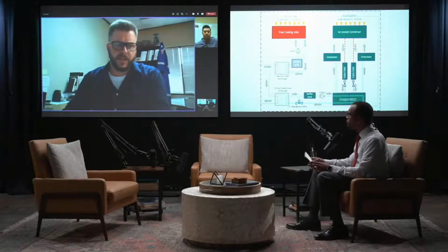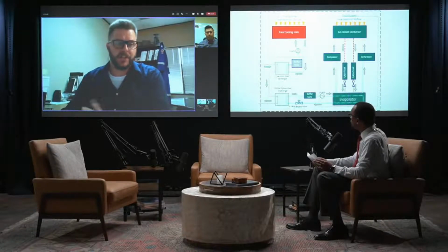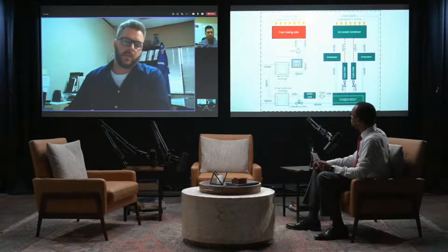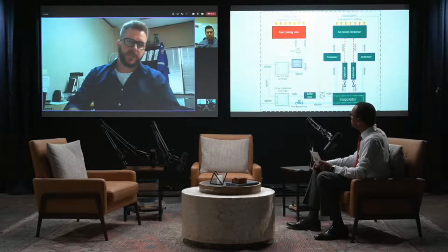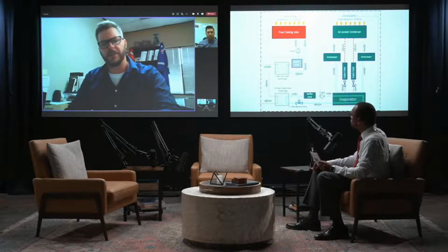And then the second stage is the HVAC system. So again, the closed loop water system. The water flows through a chiller. It's basically a refrigeration system. It's a 150-ton rated unit, so it's got a massive amount of power, or a massive amount of energy that it can take out of that water, which is just heat. So it maintains that water temperature, and then that water enters the heat exchanger with the drilling fluid. The drilling fluid enters on one side of it, the water enters onto the other side of it. The water takes the heat out of the mud and then flows back into that chiller system.